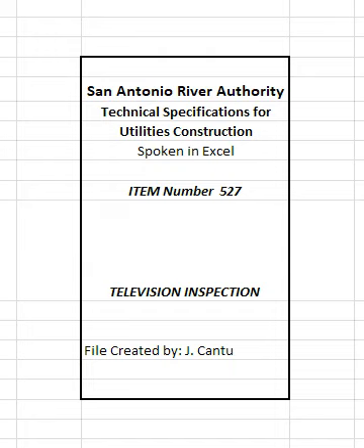The contractor shall provide a line diagram area sketch and written log for each completed segment of DVD sewer main describing the section being televised, flow and camera direction, position of service connections, description and location of failures, pipe condition, weather conditions, and other significant observations. The television inspection equipment shall have an accurate footage counter which displays on the monitor the exact distance of the camera from the center of the starting manhole.